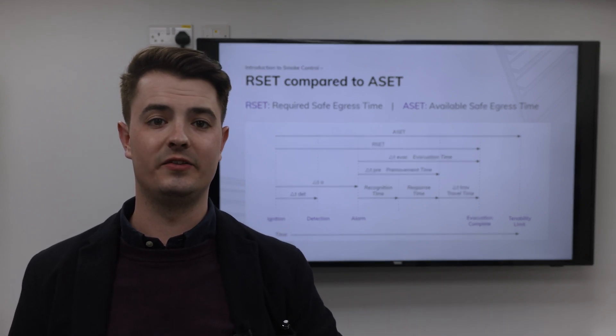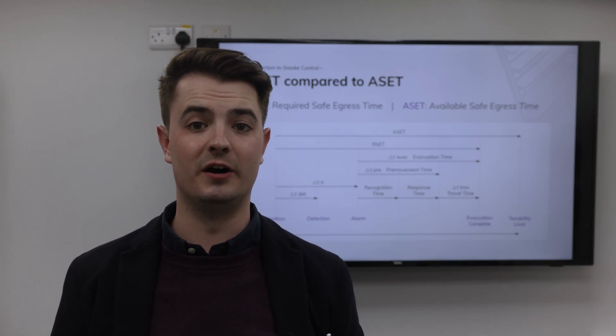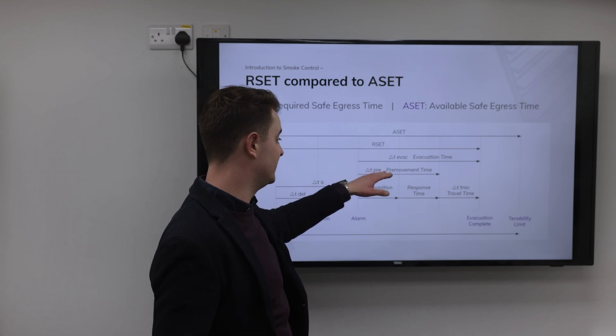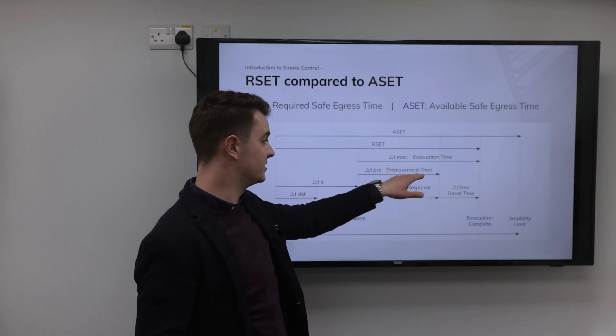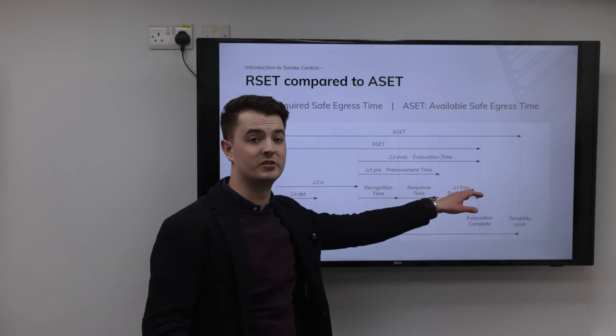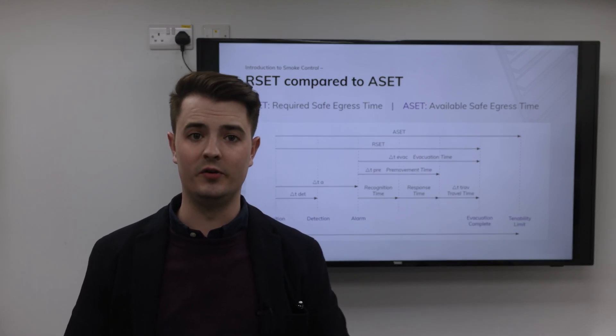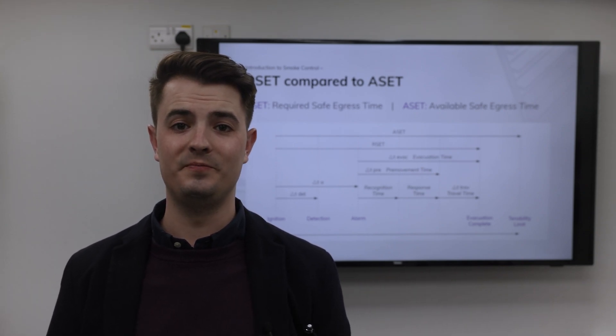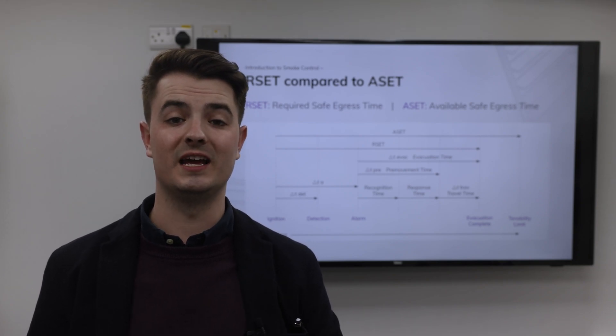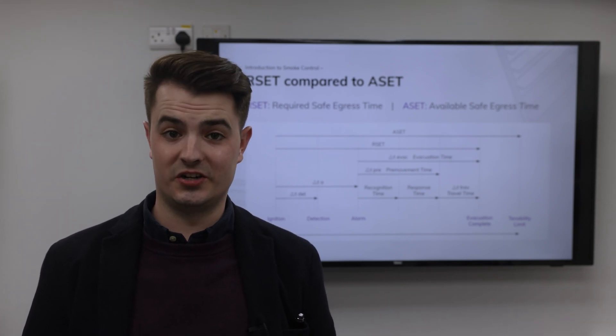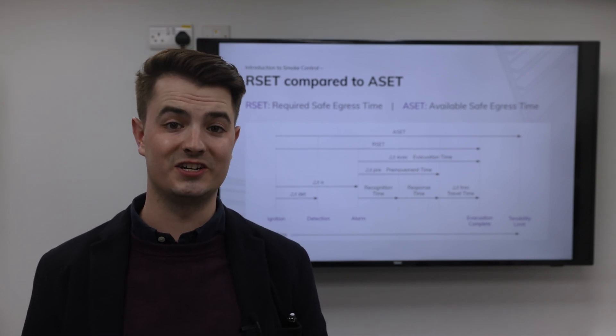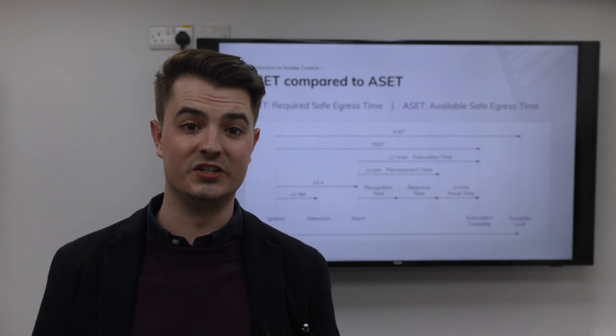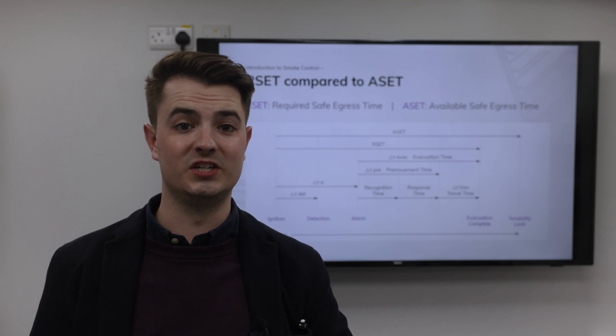When evaluating the RSET, three components need to be considered: detection time, pre-movement time, and movement time, as defined on this chart. The detection time is the time from the ignition of the fire to the alarm being raised. The detection time — and as such, the RSET — is highly dependent on the type of fire detection system provided. For example, a manual fire alarm system will likely mean a longer detection time than an automatic detection system with detection devices throughout the building.